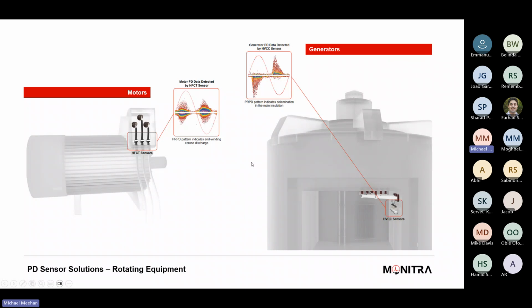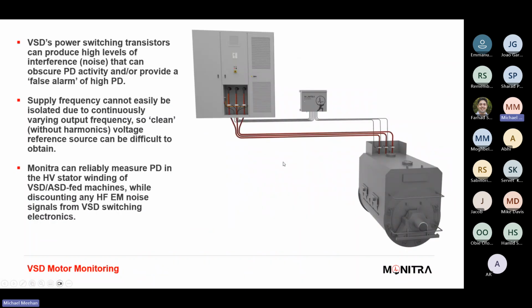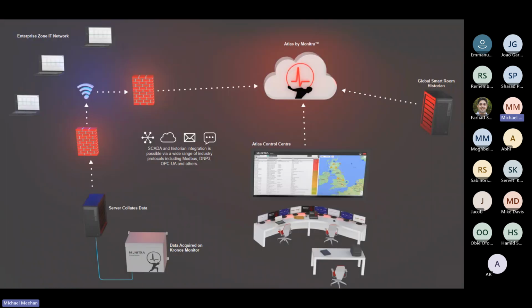In terms of where the sensors are installed at machine, so hydro generator or generators and typical machines, HFCT example, and we've gone through the patterns in some ways. These are just more examples of the installs. This is what a system might look like in terms of you've got your acquisition, which is the grey box that links into the server of the client. You've obviously got all firewalls and everything else that obviously need to be in place now.